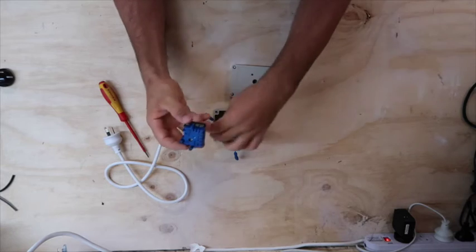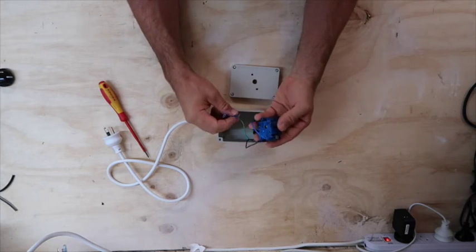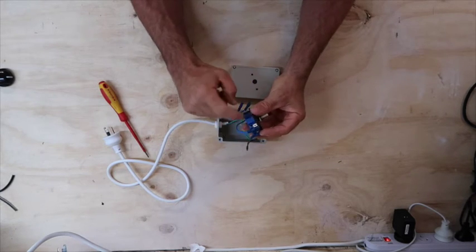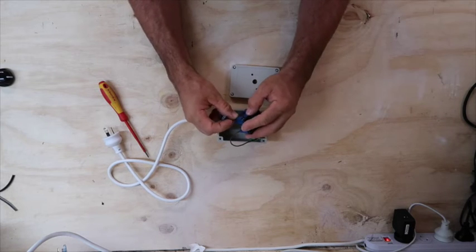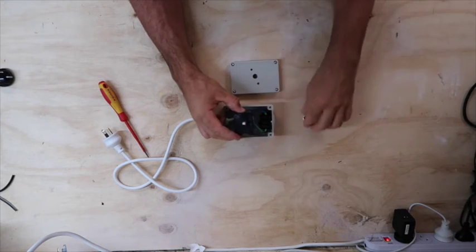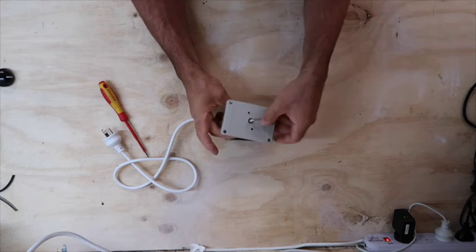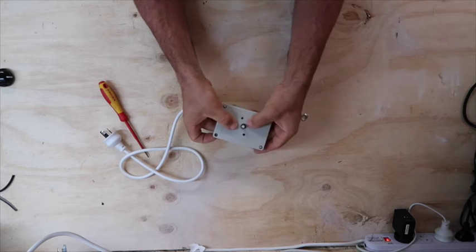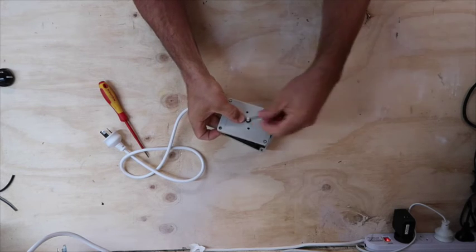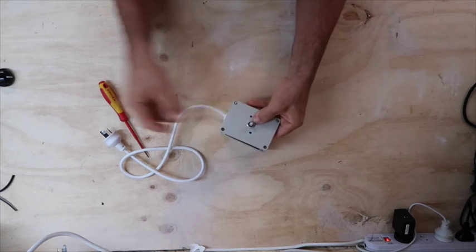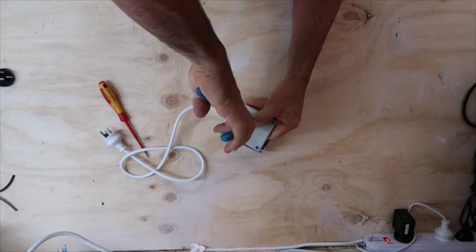So we're going to plug them in now. And they're just little tabs, six point four mil tabs, that these tab connectors go onto. And then we take the lock ring off, and insert the energy controller into the lid. And make sure that the locking keys line up through the holes. And secure it like so.